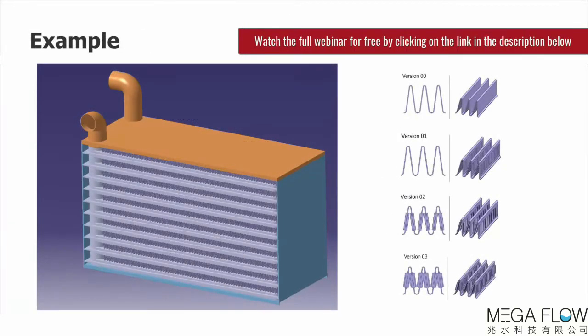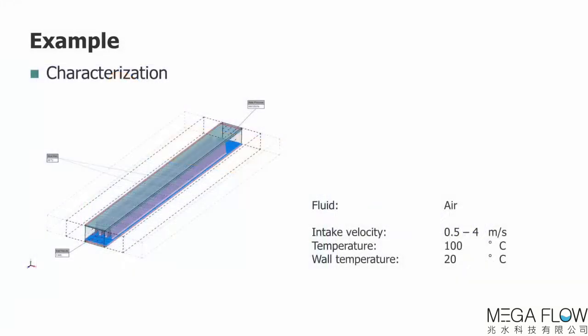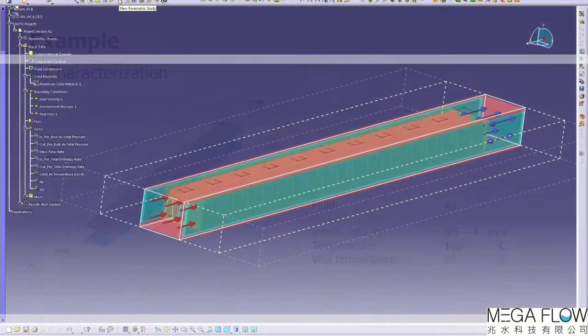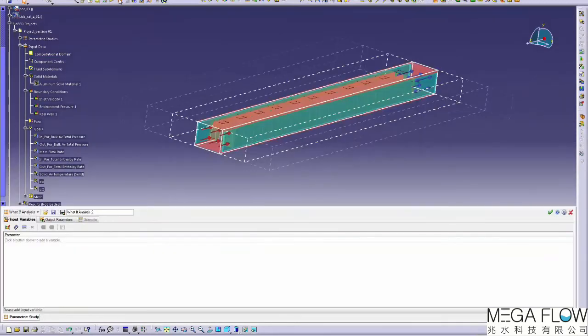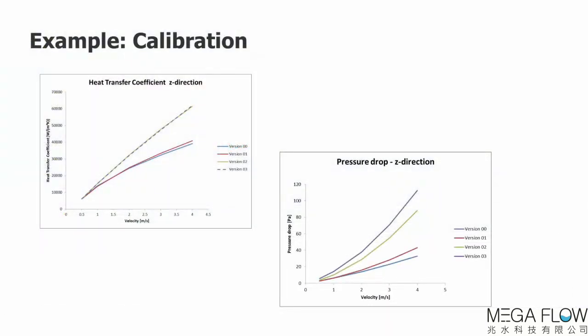Let's consider our example now. Here we have four variations of the fin geometries. The first step is to characterize the examples in terms of pressure drop and heat transfer rate. We use the FloEFD parametric study to run a range of inlet velocities. The results are shown in these charts for the longitudinal direction.